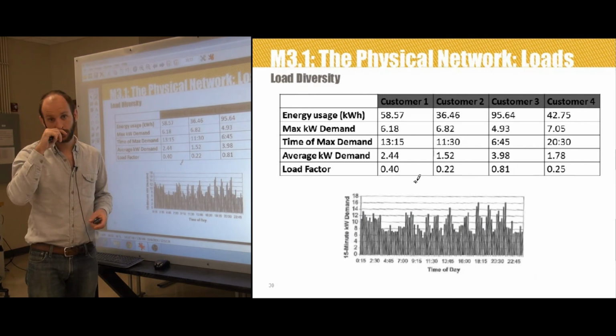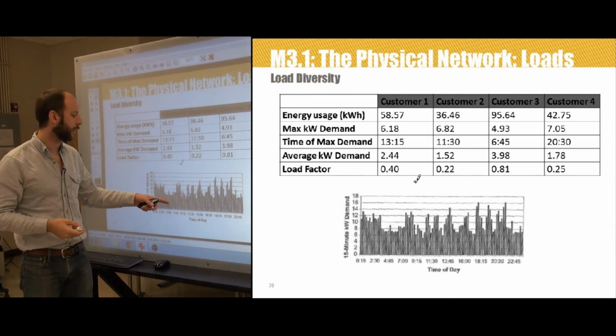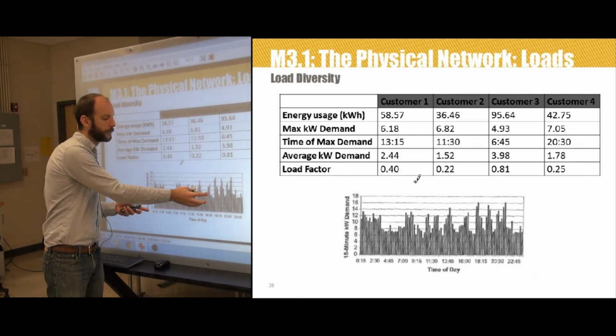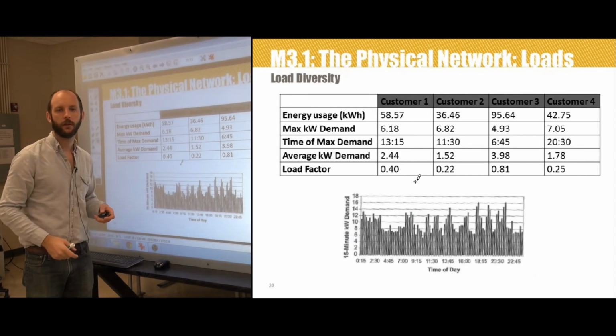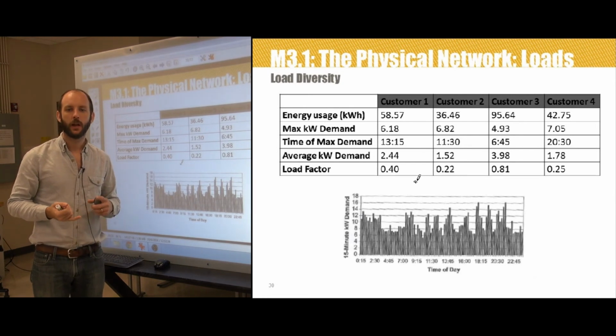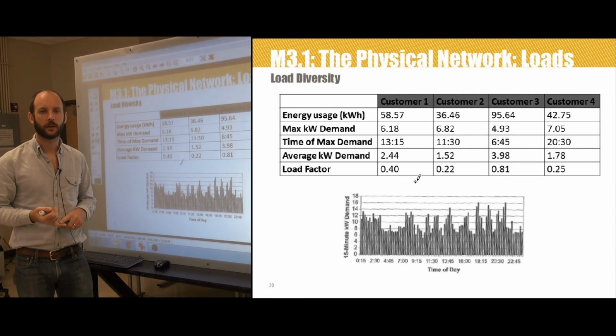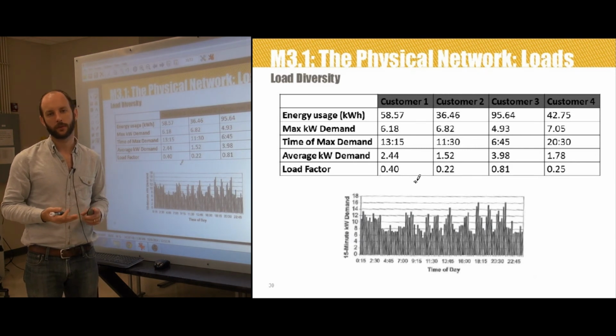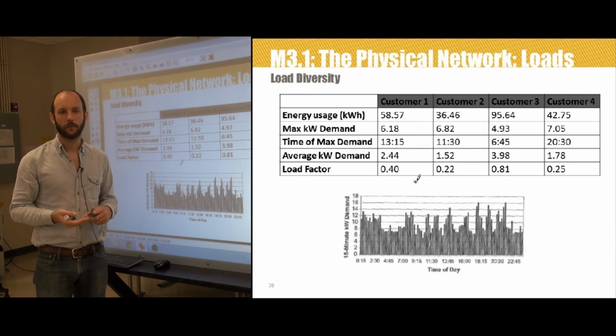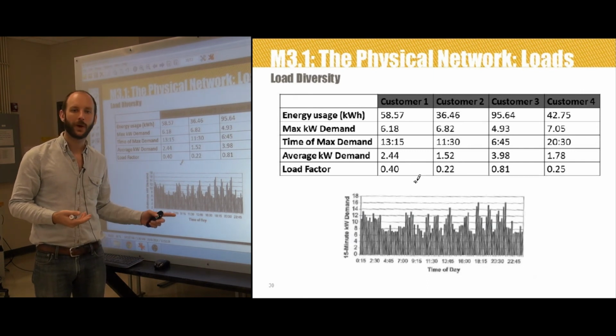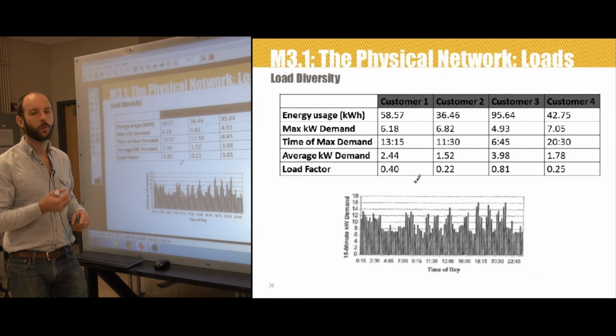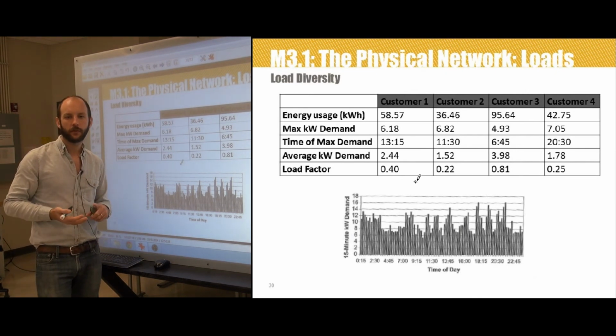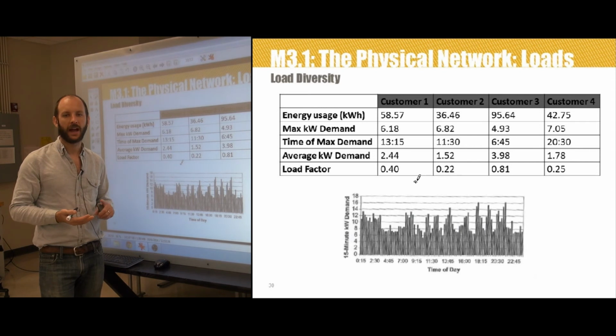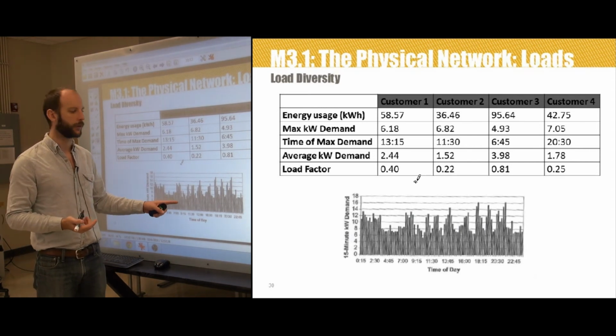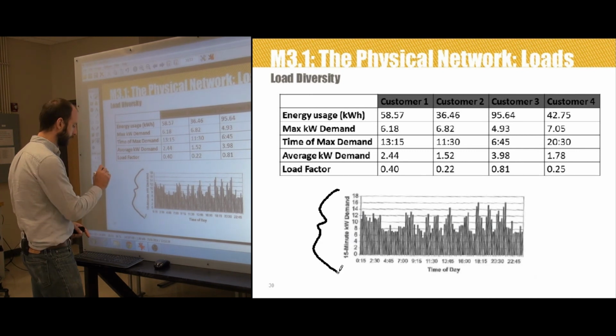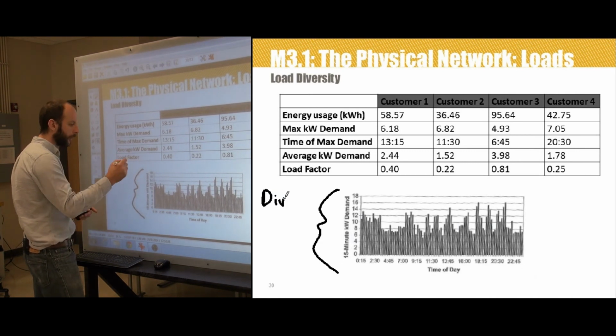So how does this data combine? Well, what we see by this graph, which is the combined 15-minute average demand curves for these 4 customers, is that the aggregate behavior is substantially different than that of an individual customer in both magnitude and temporal variation. In fact, although the magnitude will generally increase, fluctuations in the time when electricity is used will tend to decrease. When we sum the 15-minute kilowatt demands for each time interval and we aggregate for several customers, this is called diversified demand. This graph is diversified, just meaning it's been spread over several customers, right?